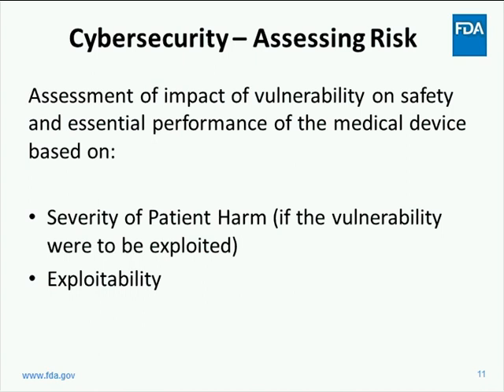Thank you, Suzanne. This is Seth Carmody, Senior Program Manager for Medical Device Cybersecurity at the Center for Devices and Radiological Health. In principle, the final guidance is about cybersecurity risk management. The guidance provides a suggested risk management framework and assessment methodology which manufacturers can use to meet their regulatory obligations under 21 CFR 820. The assessment methodology combines concepts from the FDA-recognized standard ISO 14971 and the Common Vulnerability Scoring System, known as CVSS. Together, CVSS provides medical device manufacturers with a repeatable methodology for assessing risk of patient harm due to vulnerabilities, ultimately providing a triage tool for the prioritization of remediation, as well as cybersecurity routine updates and patches.